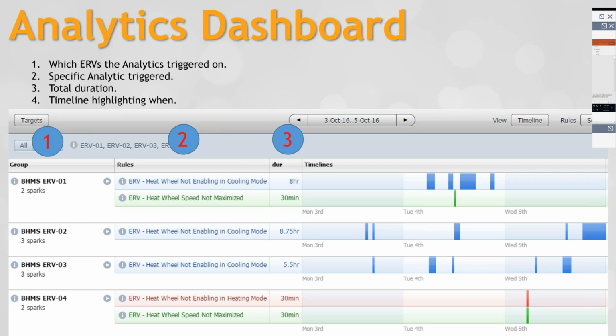We want to know how long they were triggered, how long they were out of their performance expectations, and when that happened. In this case, a specific day. I've highlighted this section in green where the heat wheel speed was not maximized, meaning there was an opportunity for the heat wheel to run, and it wasn't.